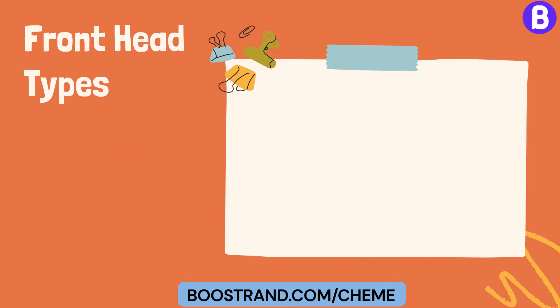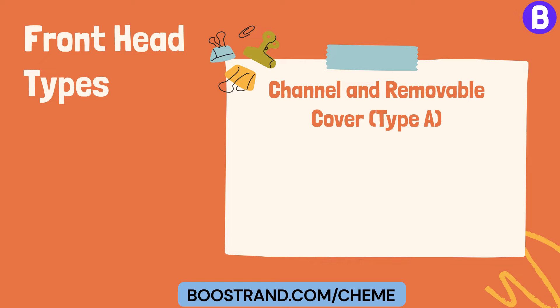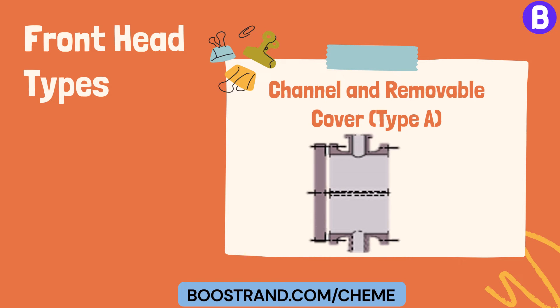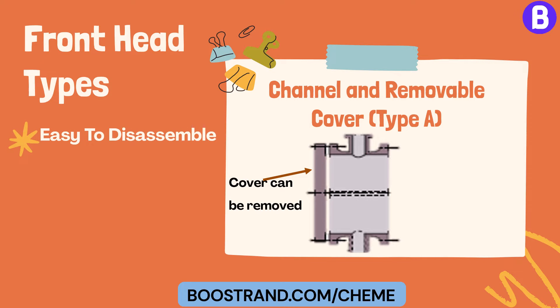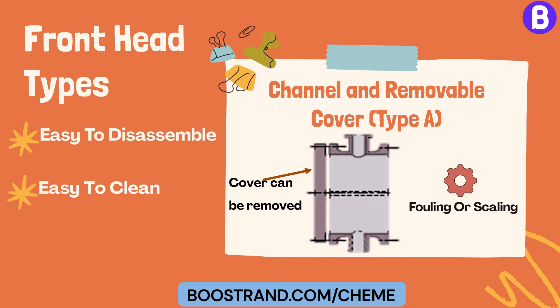Let's start talking about front head types. Channel and removable cover, Type A: this design typically consists of a shell with separate channel covers that can be removed. Type A heat exchangers are more straightforward to disassemble, allowing easy access to the tube bundle for cleaning or repair purposes. They are suitable for applications with fluids that may cause fouling or scaling, requiring periodic cleaning.